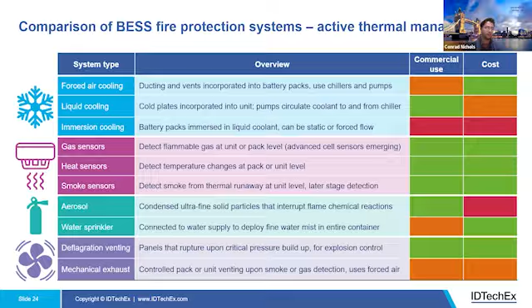So just to touch on cooling, this is fundamental to BESS temperature control. It ensures that the battery operates within the cell's operating temperatures. It helps to prevent hotspot formation and temperature gradients, which can induce thermal runaway.